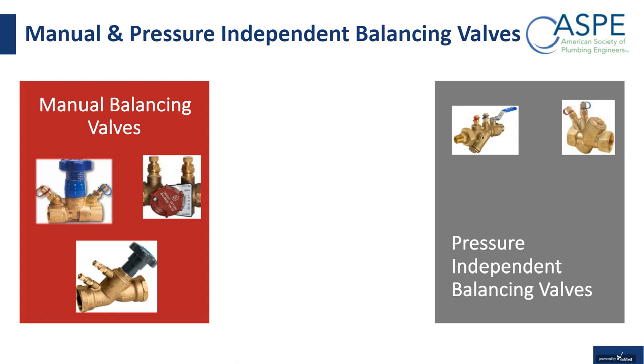So here's just a little chart that basically shows you the graphics of the different types of balancing valves. On the left here, we have the manual balancing valves, which you can notice because they have pressure ports and a knob on them. So they're basically the manual valves that you measure the pressure across to try to determine the flow.